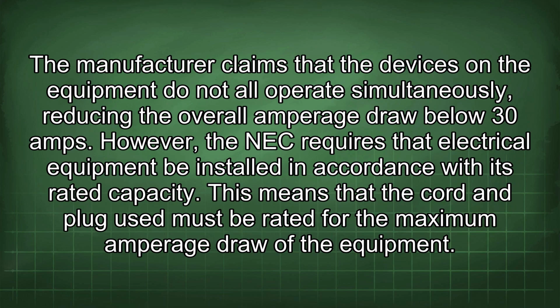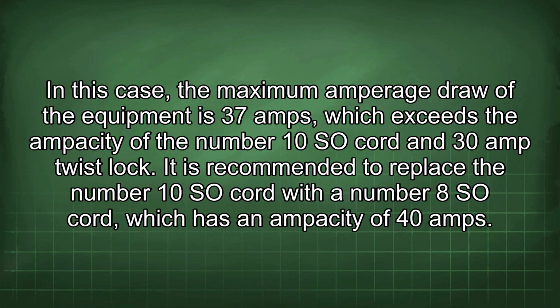The manufacturer claims that the devices on the equipment do not all operate simultaneously, reducing the overall amperage draw below 30 amps. However, the NEC requires that electrical equipment be installed in accordance with its rated capacity. This means that the cord and plug used must be rated for the maximum amperage draw of the equipment. In this case, the maximum amperage draw of the equipment is 37 amps, which exceeds the ampacity of the number 10 SOW cord and 30 amp twist lock.